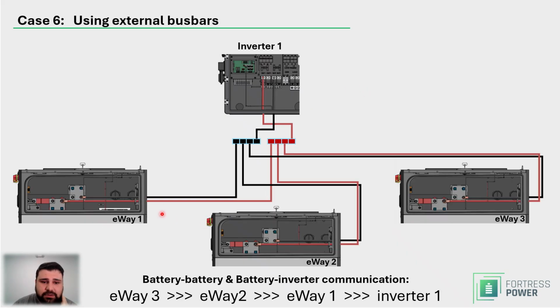So for 3, this is what you would do. For 4, for 5, for 6, this would be the same principle, right? And I know that with 3, yes, you can use the internal bus bars. It's just the slide is just this big. I cannot squeeze in 20 batteries in here. So if the principle here is clear for 2 or 3, I'm sure it will be clear for you for 5, 6, or 7 batteries or whatever have you. The communication, again, very simple: eWay 3 to eWay 2, eWay 2 to eWay 1, and eWay 1 to inverter 1.